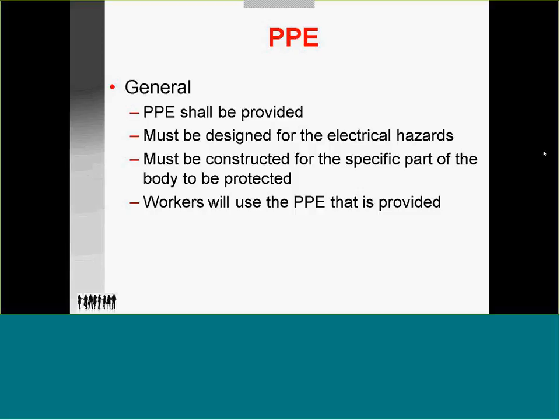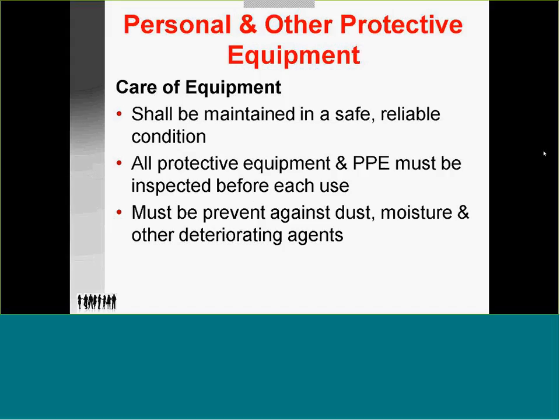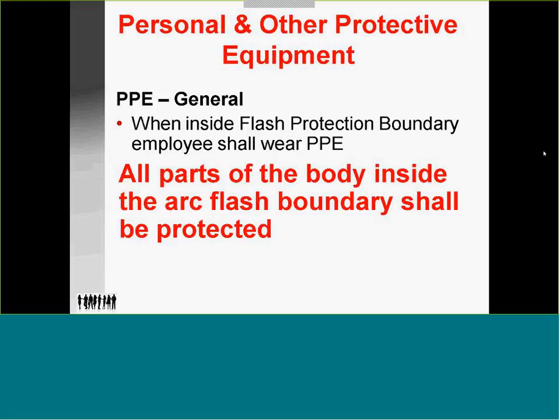PPE in general must be designed for the electrical hazard and must be constructed for the specific part of the body to be protected. Workers will use the PPE that is provided. So, the employer must provide and the employee must wear. Equipment shall be maintained in a safe and reliable condition. Take care of your PPE so it'll take care of you. If you get oil on it, it becomes an igniting source, and an arc flash event can start it to burn. All protective equipment, PPE, must be inspected prior to use. It must be protected against dust, moisture, deteriorating agents, solvents. Any of this will reduce the arc rating value.